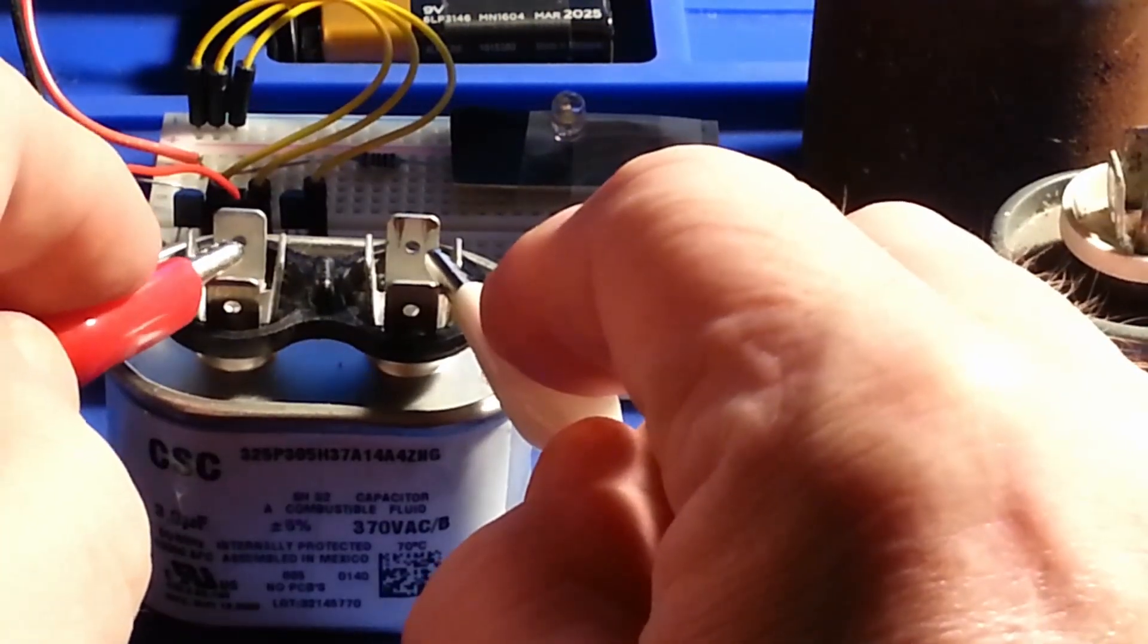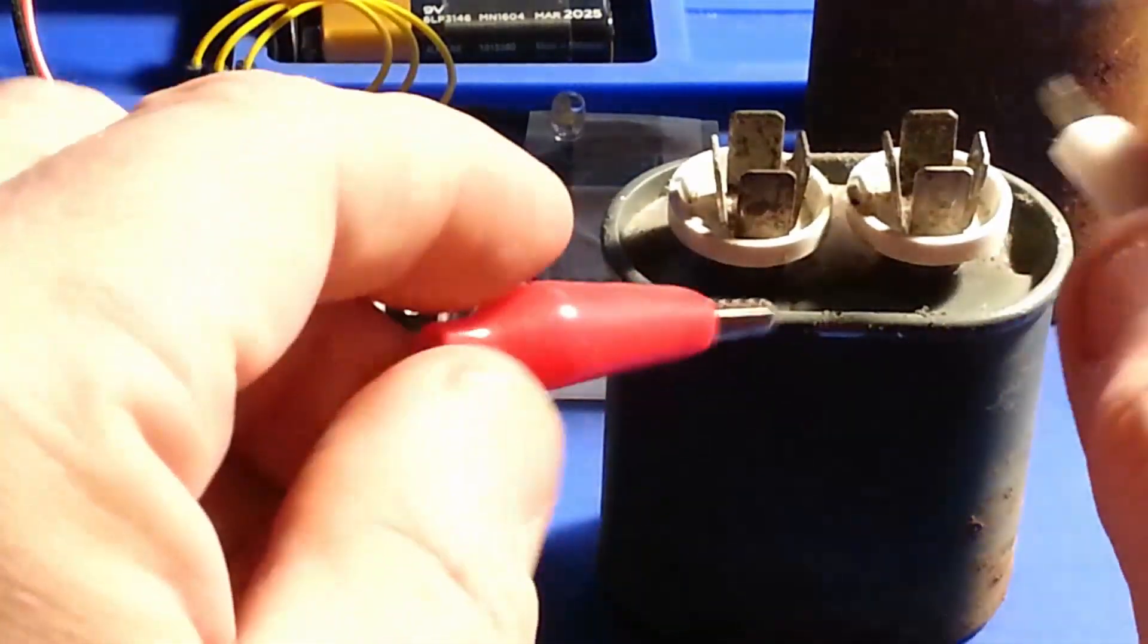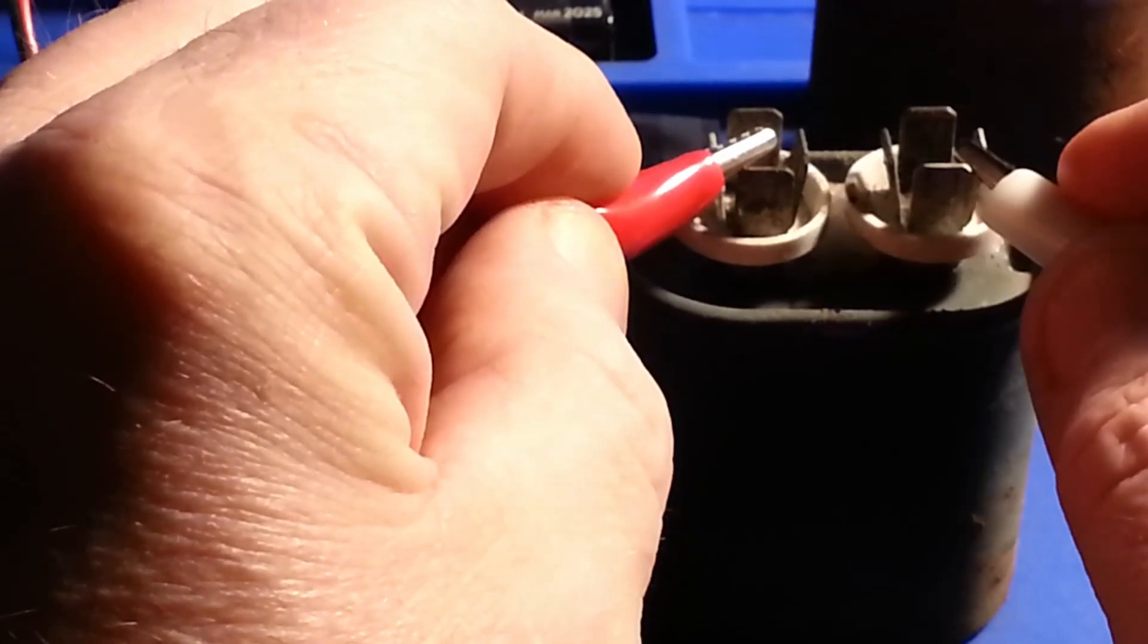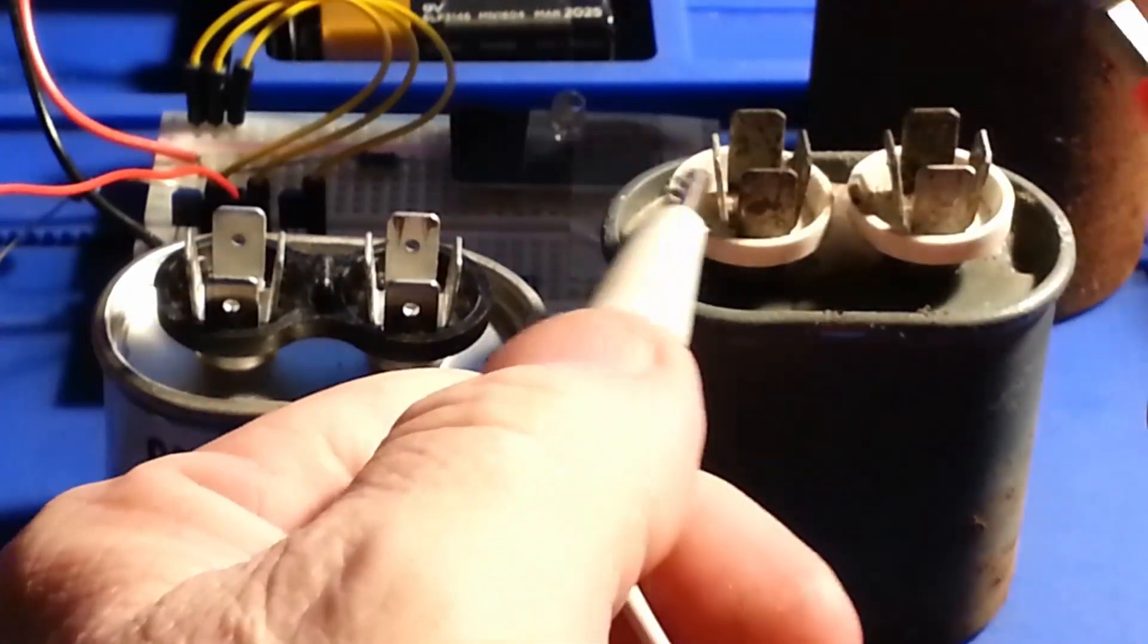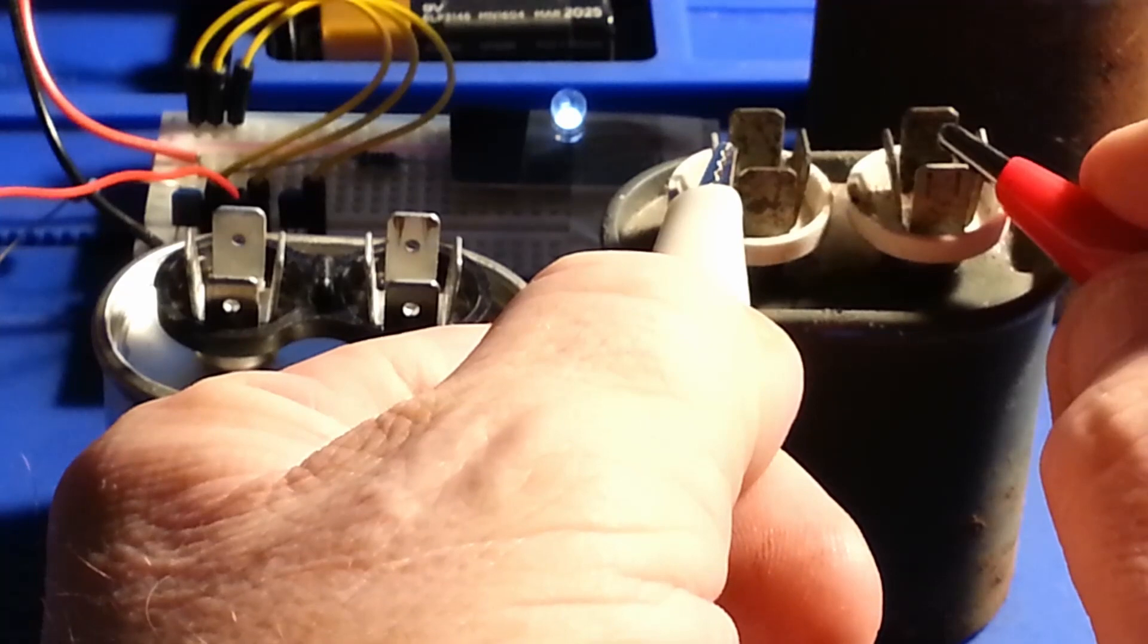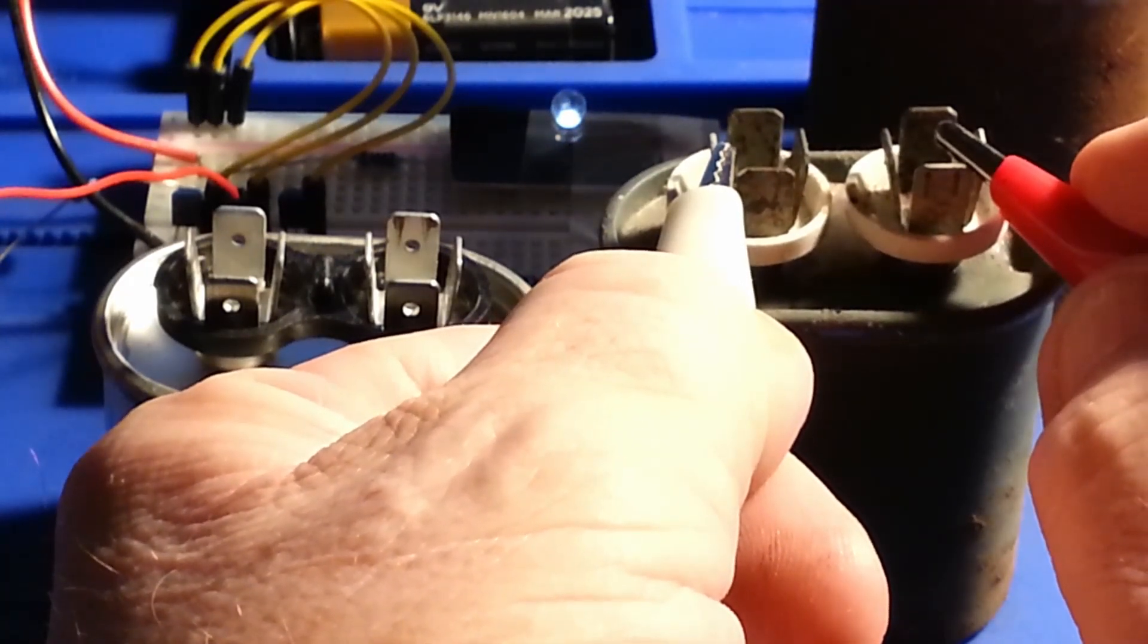In the middle position, this is also showing no internal leakage. And the new three microfarad and the old, it shows as you can see, I'll get my big hands out of the way here.